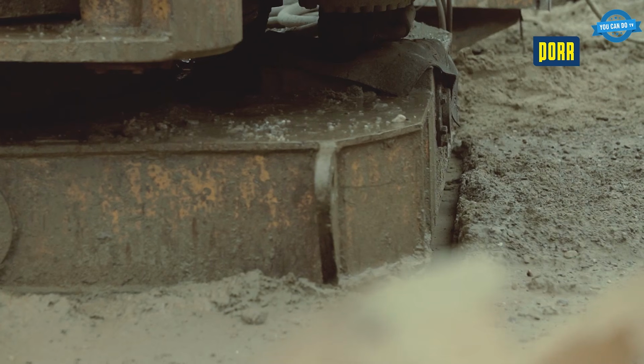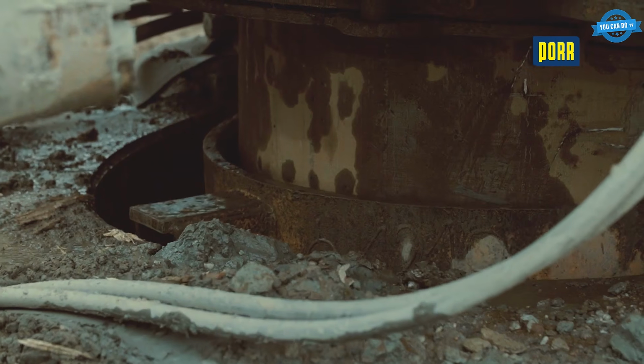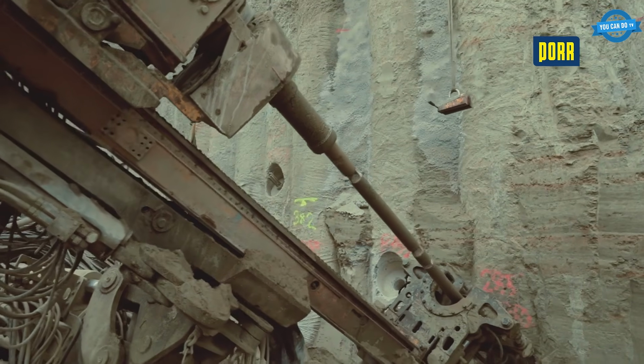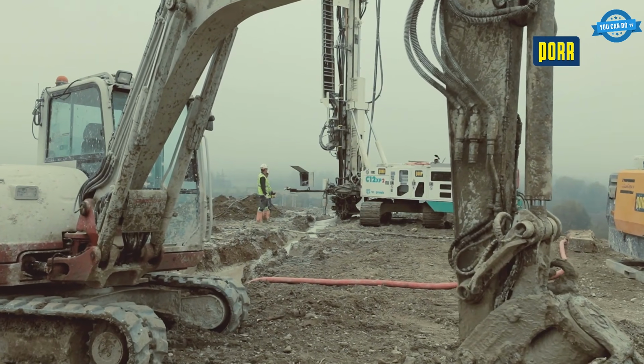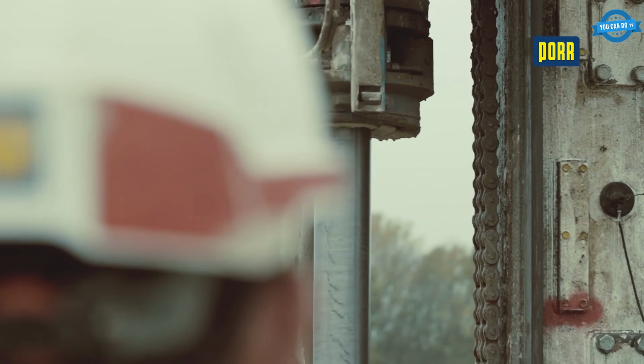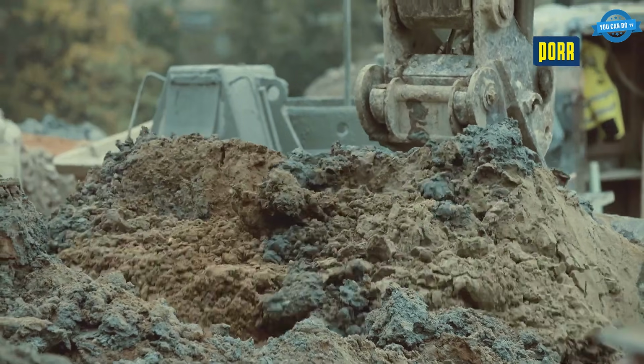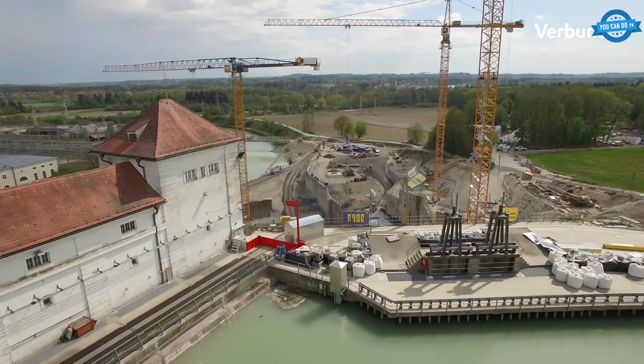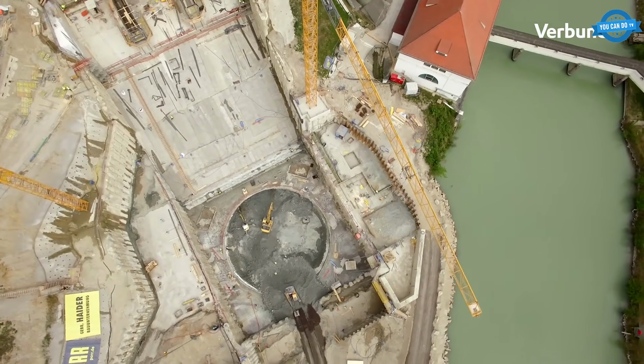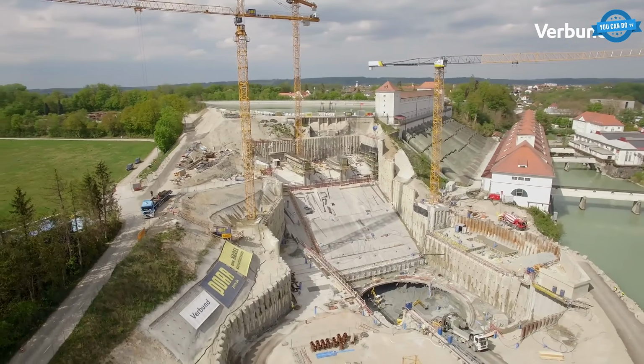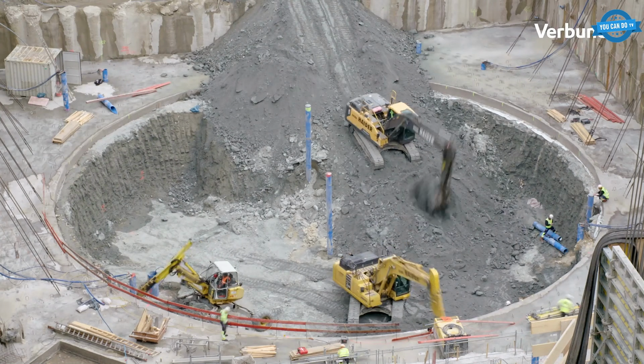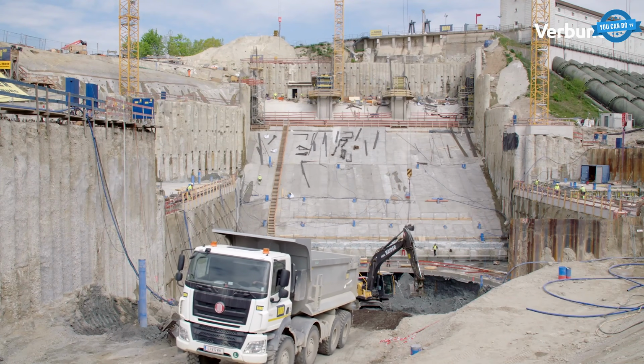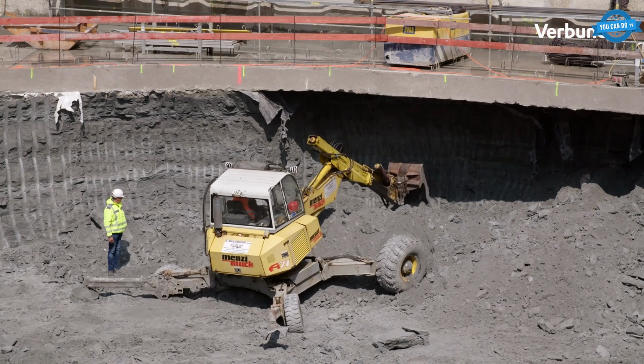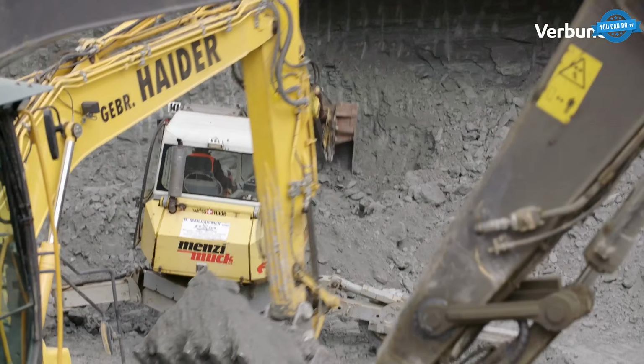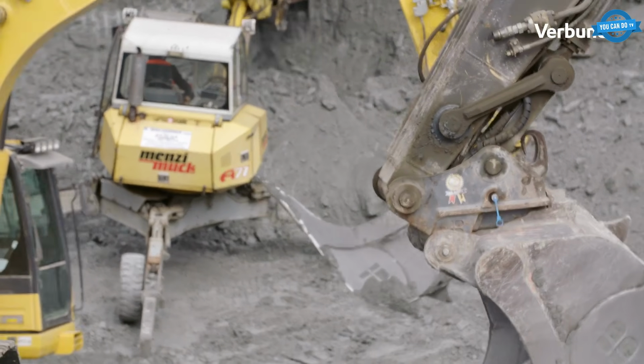The excavation uses every technique in the specialty foundation toolkit: bored piles, diaphragm walls, ground anchors, jet grouting, backed by heavy dewatering to keep the 30-meter pit open. A 100,000 cubic meter excavation beside the power plant, secured by 420 bored piles, each running 70 meters deep. That is the first half of Germany's largest hydropower renewal project, valued at 250 million euros.